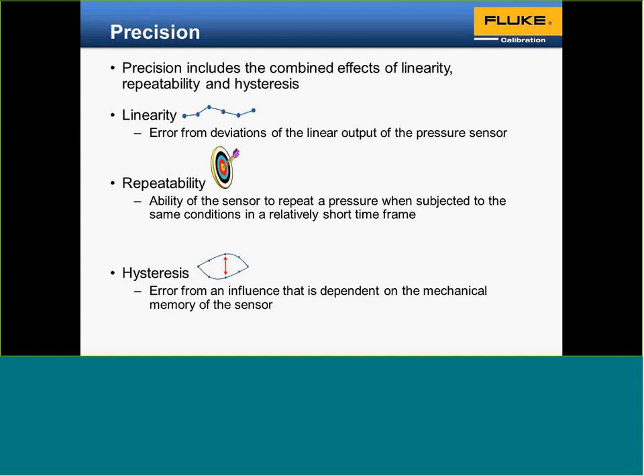Repeatability is part of the sensor spec, which is the ability of the sensor to repeat under the same conditions in the same time period. Hysteresis is the mechanical measure. Sometimes zero drift of the sensor can contribute to hysteresis, which may make hysteresis larger, so you take away zero drift from hysteresis. Sometimes they're combined into one.